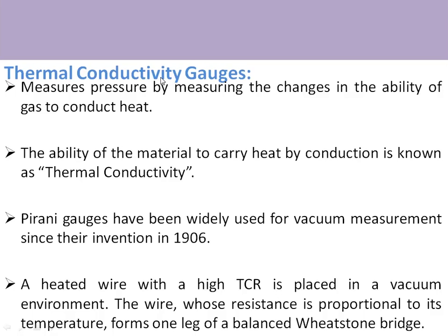Thermal conductivity gauges are discussed in this video — specifically the Pirani gauge. In the Pirani gauge, the ability of gas molecules to carry heat is used to measure pressure. It measures pressure by measuring the change in the ability of the gas to conduct heat. Higher pressure means more gas molecules are present and more heat will be transferred. The ability of a material to carry heat by conduction is known as thermal conductivity, and the Pirani gauge based on this principle has been widely used for vacuum measurement since its invention in 1906.